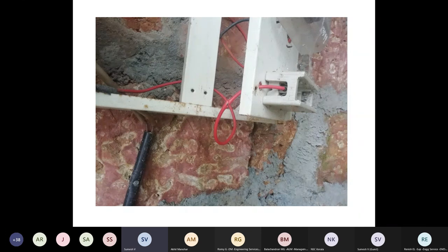So what is the actual problem here? The meter, cutout fuse or main switch is not supposed to be fixed on a hinged door. It should be inside the box. No live part should appear on a hinged door. That is the major reason for the accident.